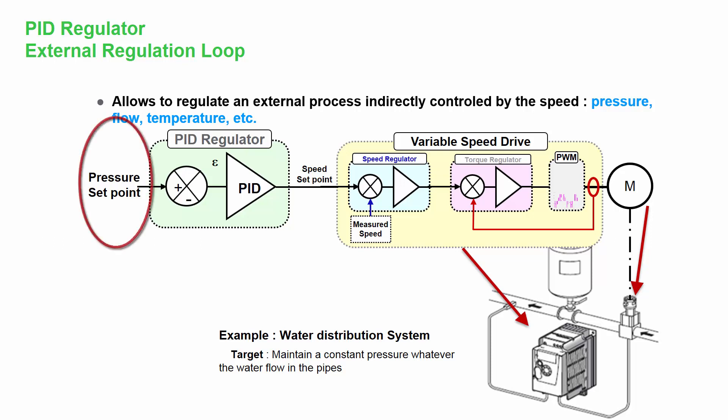So input of PID regulator is a pressure setpoint and output is a speed setpoint. Additionally, we have to connect the feedback to a PID regulator, which would be the pressure sensor from our water distribution system.